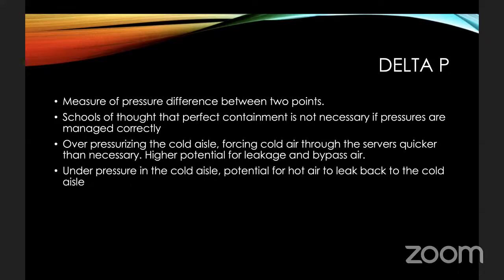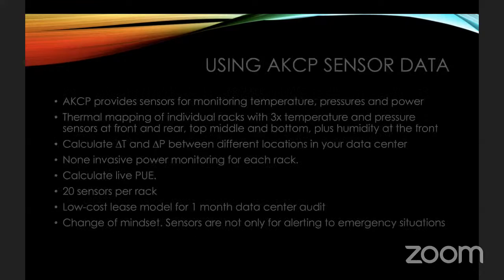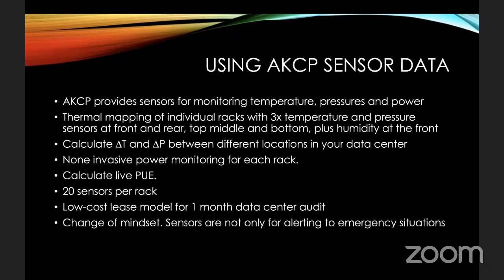So if you overpressurize the cold aisle, which is basically your CRAC pumping out full capacity all the time, regardless of what the servers are doing, then you're going to be forcing cold air through the racks. That is unnecessary. Those servers don't need that cold air. Conversely, if your air supply is too low, the servers are going to be sucking and they're not going to be getting the cold air that they need. So under-pressurization of the cold aisle is a problem, and over-pressurization of the cold aisle is also a problem. So you can use the AKCP sensors to monitor the temperatures, the pressure, and the power.